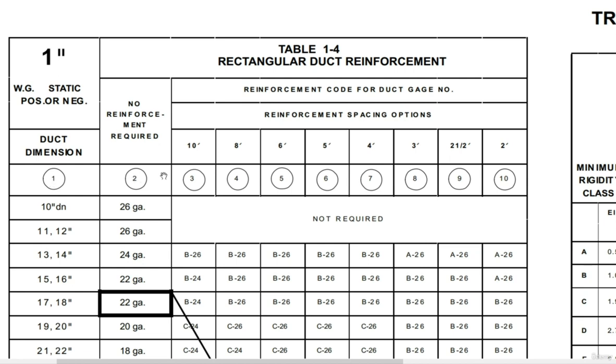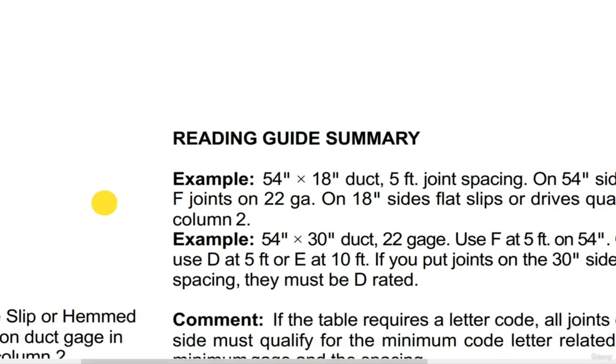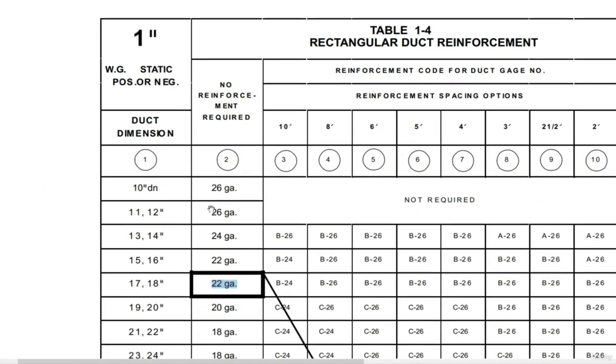Note that the values in the circles denote the column number. Columns 3 to 10 give you the reinforcement code for duct gauge based on the reinforcement spacing options. We are using the reinforcement option of 5 feet, so I use that as my column entry point and the duct dimension as my row point, then cross them to obtain the required value. For the 18-inch duct, which represents the duct height, it falls between 17 and 18 inches. I can see that no reinforcement is required if I use gauge 22, as noted: flat slips or drives qualify per column 2, meaning no reinforcement is required.